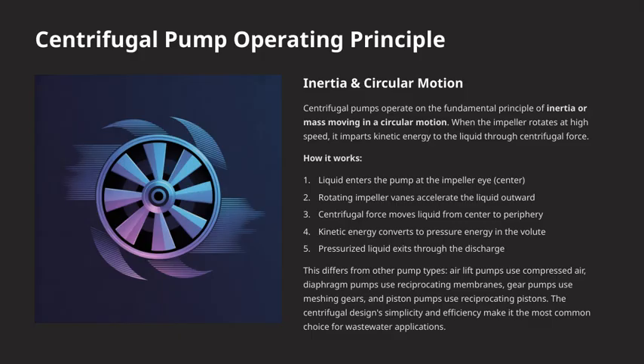What makes centrifugal pumps stand out compared to other types? Well, they are simple in design and highly efficient. Unlike airlift pumps that use compressed air, diaphragm pumps with reciprocating membranes, gear pumps with meshing gears, or piston pumps with reciprocating pistons, centrifugal pumps rely on this circular motion and inertia. This simplicity and efficiency are why they are the most common choice for wastewater applications and many other fluid transfer needs. They are reliable, easy to maintain, and capable of handling large volumes of fluid with minimal energy loss.